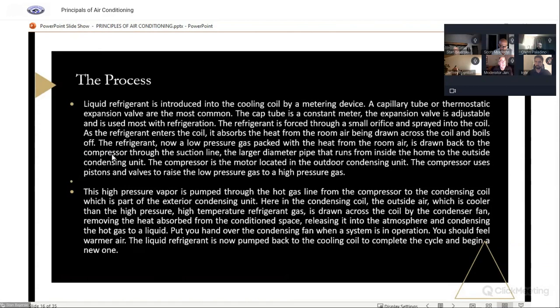So there's got to be a metering device for an air conditioning system and a refrigeration system. On a window unit, it's usually a capillary tube, which is a constant pressure metering device. And on central air, it's probably an expansion valve, which can be adjusted. So we force it through these metering devices and spray it into the coil. As the refrigerant enters the coil, it absorbs the heat as the fan blows the room air across the coil and boils off. So at that point, it's now a low pressure gas packed with the heat from the room, and it's drawn back to the compressor through the suction line, which is the bigger line going outside.